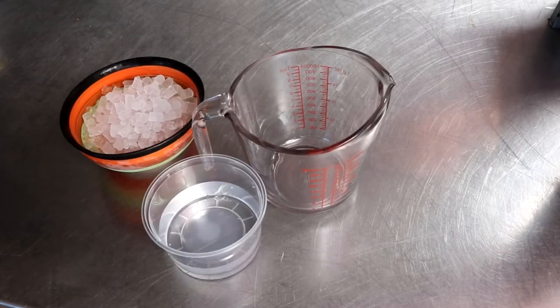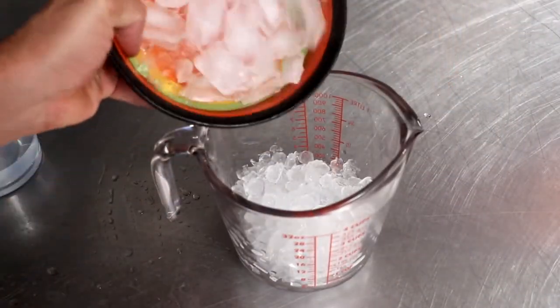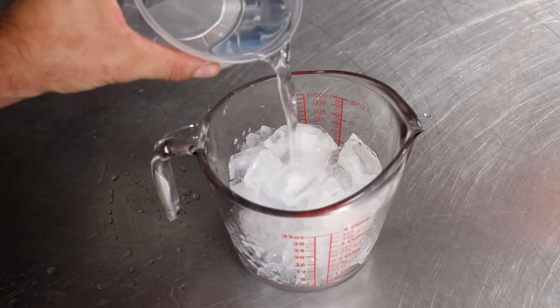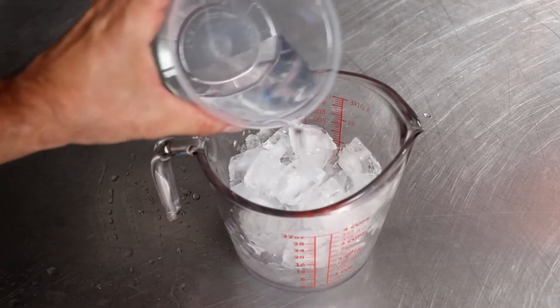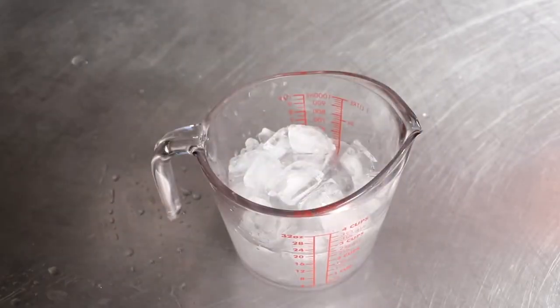To calibrate the temperature controller, what we want to do is we want to make an ice water bath. Basically, 75% ice, 25% water, and then we're going to wait 10 minutes. This should bring the temperature down to 32 degrees.